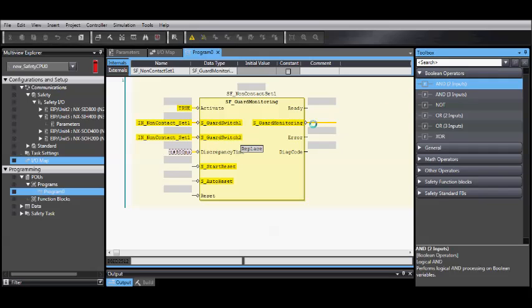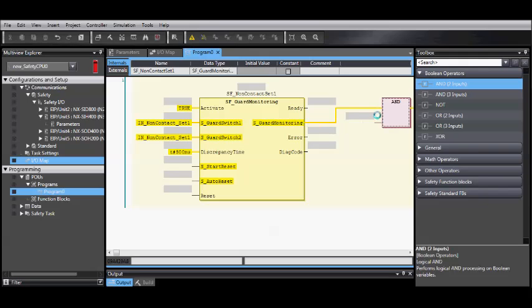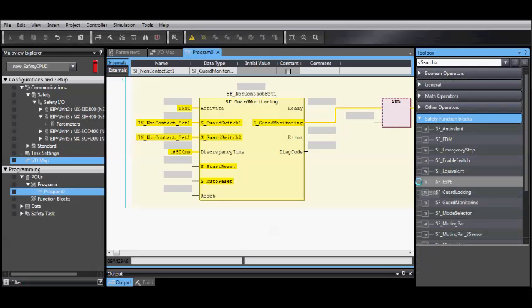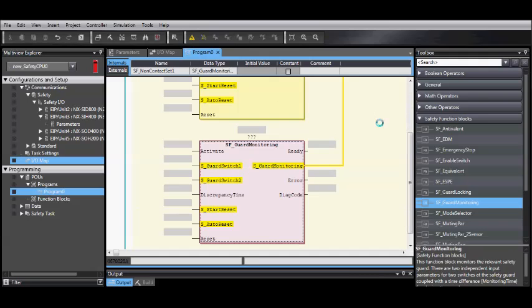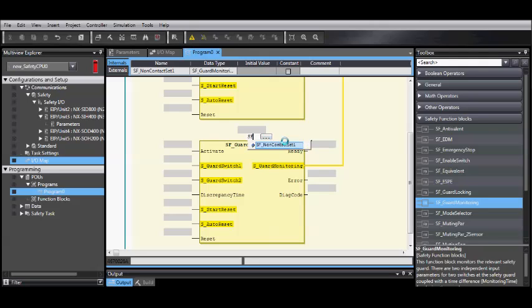Since we have two sets, we need to go to Boolean Operator, and for the output, drag and drop the AND to input. Then go back to our Safety Function Blocks, and drag and drop the Guard Monitoring onto the second input of the AND function block.